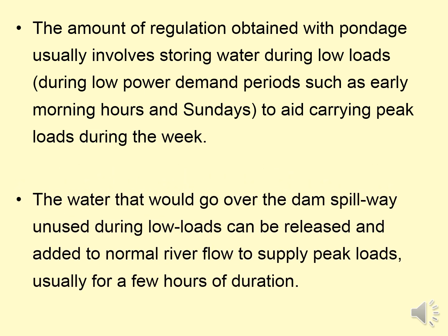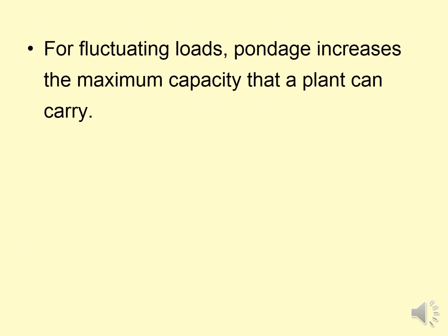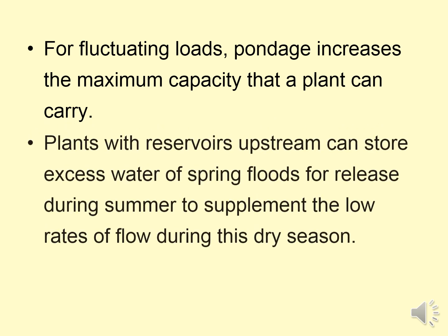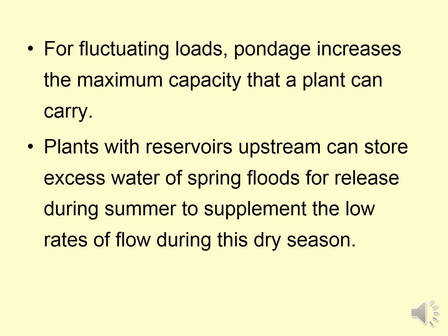So water that would go over the dam spillways unused can be stored in this pondage. For fluctuating loads, pondage increases the maximum capacity that a plant can carry. Plants with reservoirs upstream can store excess water of the spring floods for release during the summer to supplement the low rate of flow during the dry season.